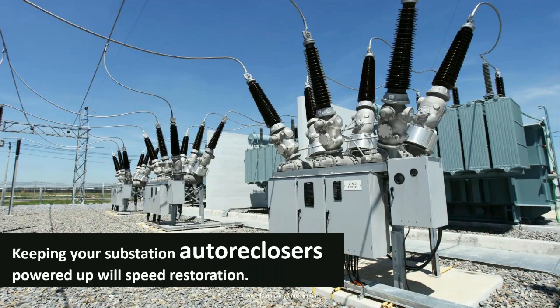As you know, substations are backed up by banks of batteries to keep their control and SCADA-based control switches operating, to be able to first open the breakers when the transmission lines are down. So when the electricity comes back, they can gradually close and do a gradual load connection. Otherwise, there's a problem of a high spike.